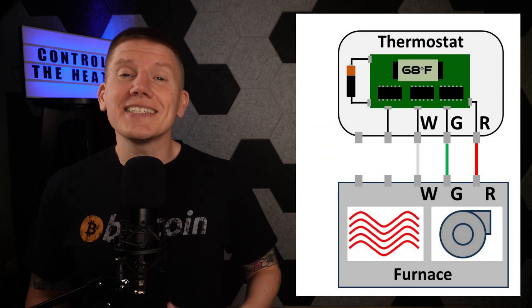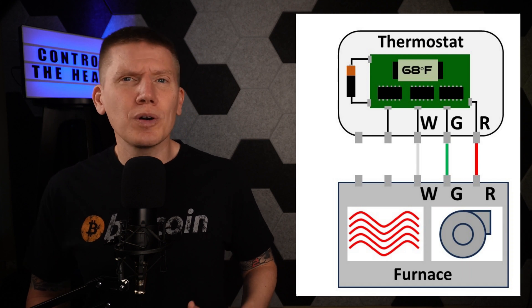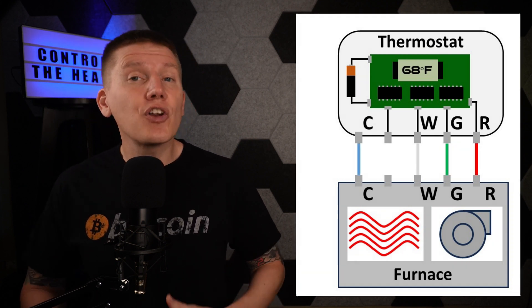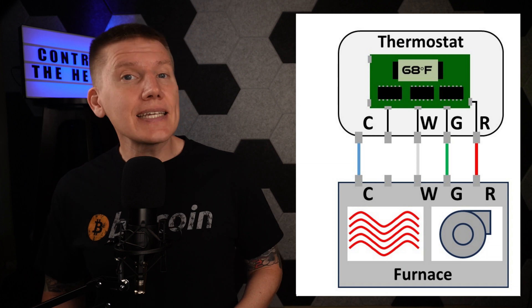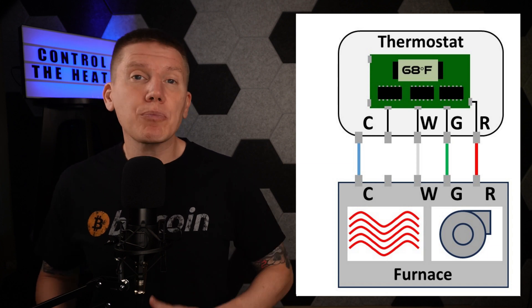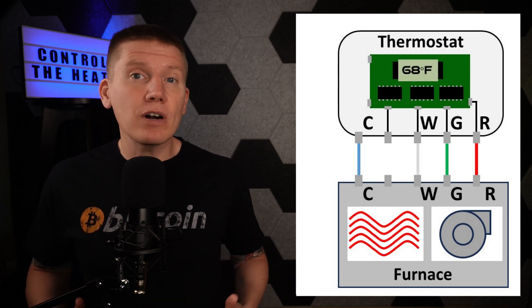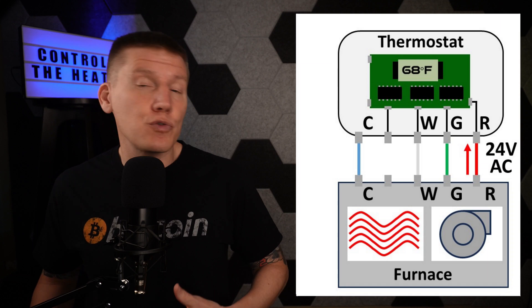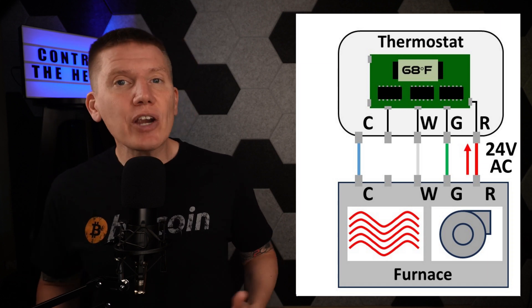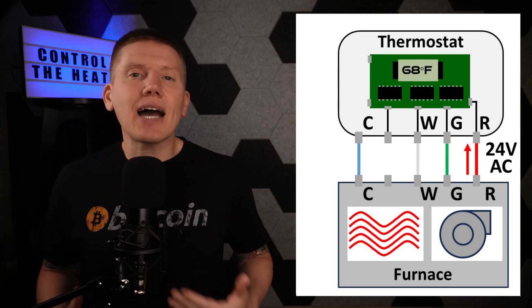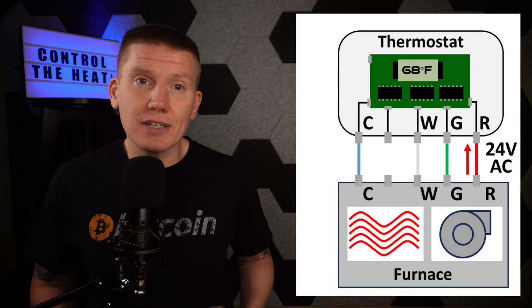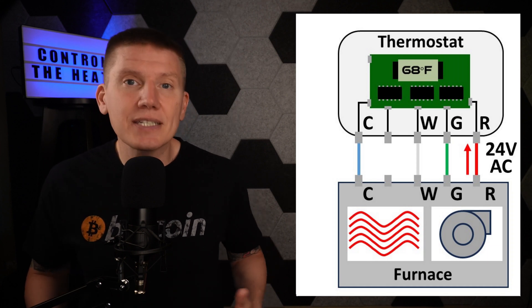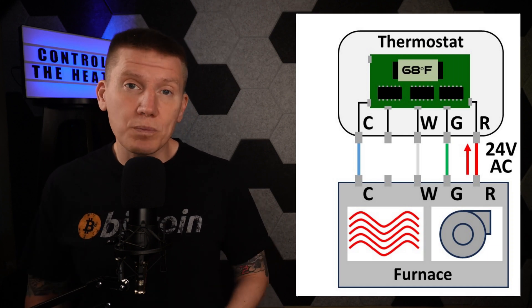The next wire is the C or blue wire. In some thermostats there is no battery — instead, the thermostat pulls its power from the furnace 24-volt power provided through the R wire. The C wire is just a common, which closes that circuit. The C wire isn't always present, particularly in older homes.